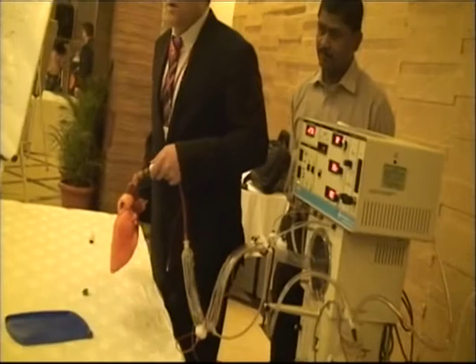What's that? Oh, reduce the frequency for oxygenation? Okay. So we're going to increase the mean airway pressure, because that might come next, though. By increasing the mean airway pressure, we're going to turn that up a little bit. So maybe 27 isn't enough. This is a larger baby. It's very sick. So I've gone up to 40. Even in a term sick baby with pneumonitis, I've gone up to 40. It's not the pressure, it's the amount of volume that's being provided in the lung. But you should never really have to go much above 25 for most infants.